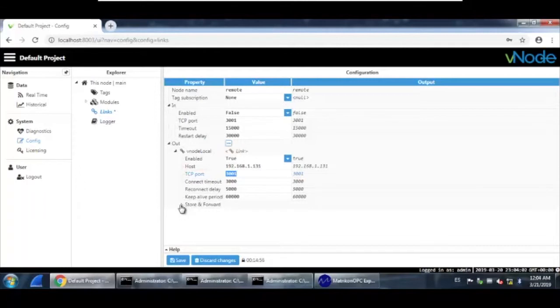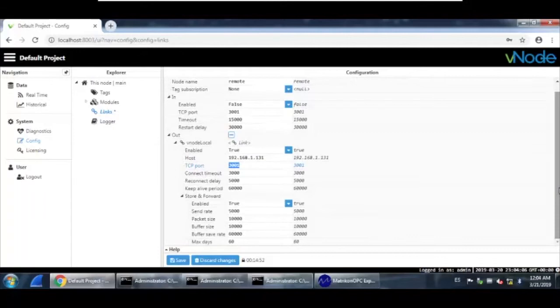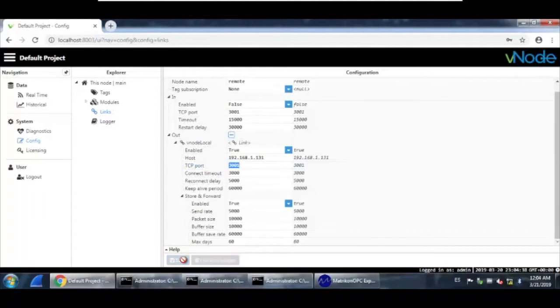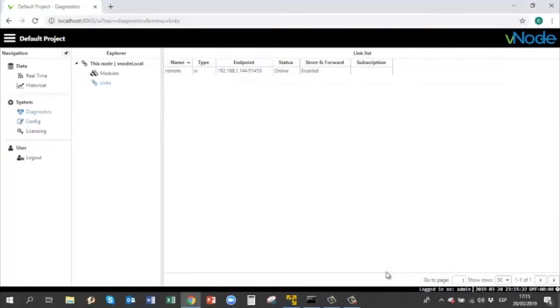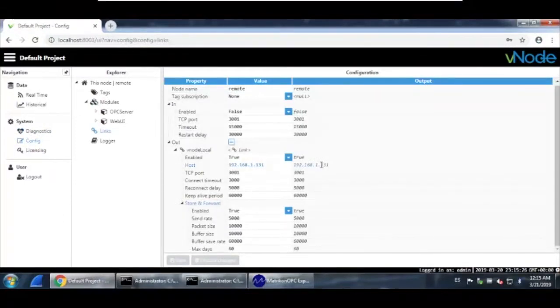The most important thing is to set up the store and forward feature. This means that once the connection experiences any network failure, this Vnode will act as a buffer and collect the same information and log it locally. Once the connection is re-established, this information will be sent to the local Vnode with the same timestamp. Set store and forward to true, also enable it, and you can leave the other parameters as default. Hit save.